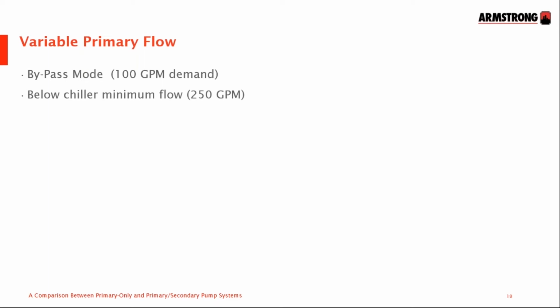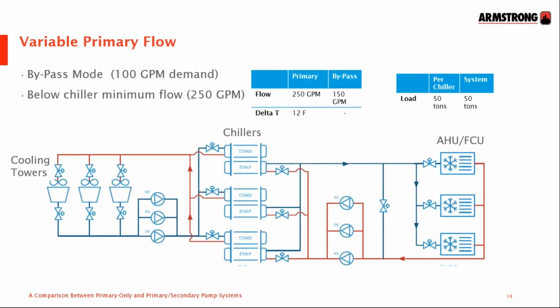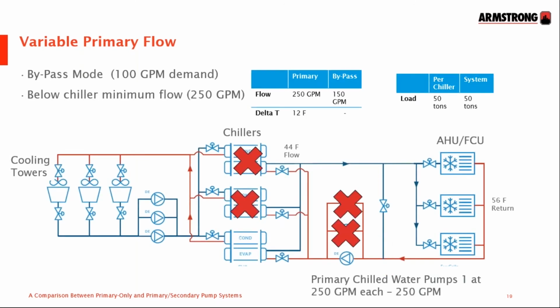As soon as the system flow, as measured by a flow meter, in many cases the Armstrong design envelope pump, which measures flow and can communicate that number to a building management system, drops below 250 GPM, the building controls will open up this bypass line here. So you'll be getting 150 gallons a minute going through the bypass, 100 gallons a minute through the load, a total of 250 gallons a minute, safeguarding the chiller here and preventing it from freezing up.